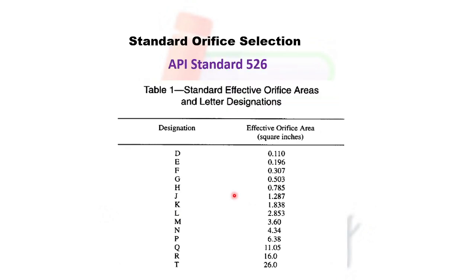After calculating the orifice size, we have to use API Standard 526. For example, if our calculated size is 0.09, we would select orifice designation D, because 0.09 is less than 0.11. Every orifice size less than 0.11 would require an orifice designation of D. If our calculated size exceeds 0.11, we would go to orifice size E. This is the table of standard orifice sizes available in API 526. After calculating the orifice size, we select the required standard orifice from this table.